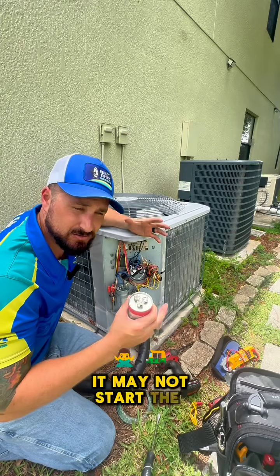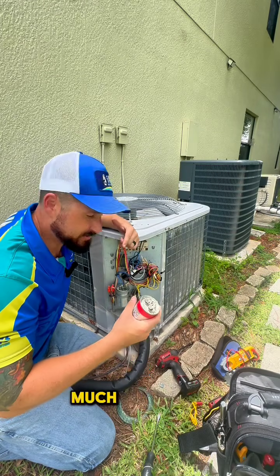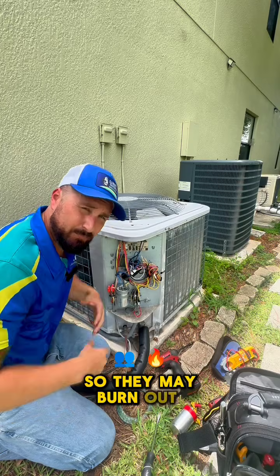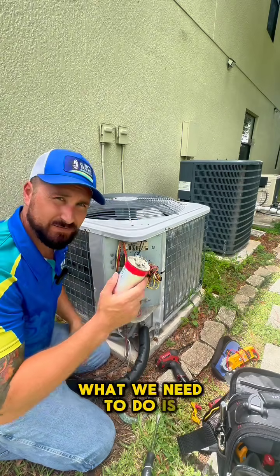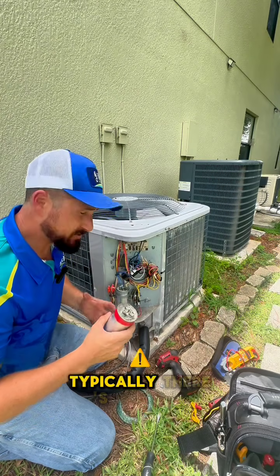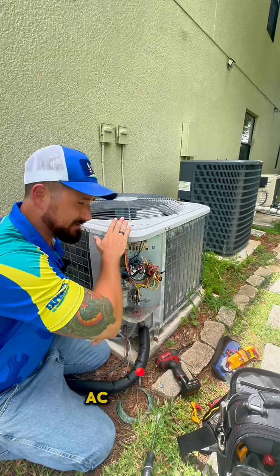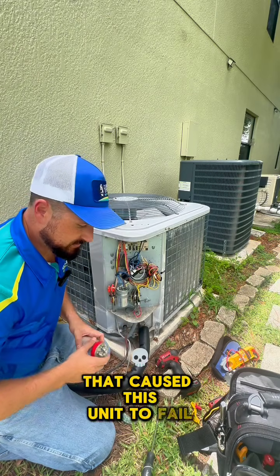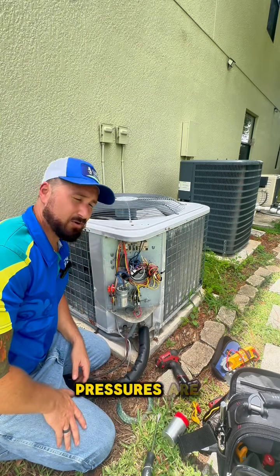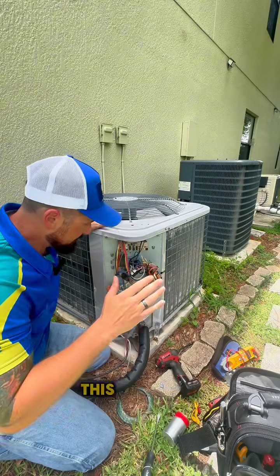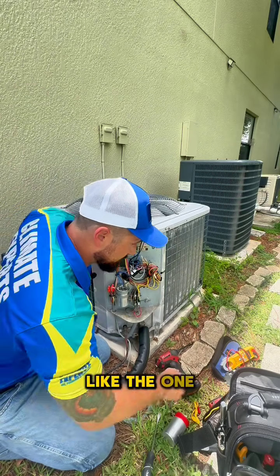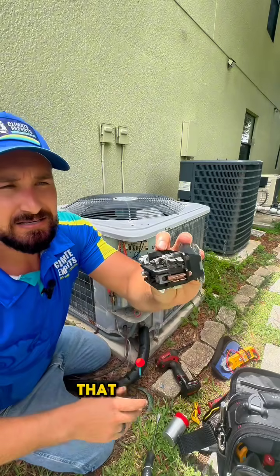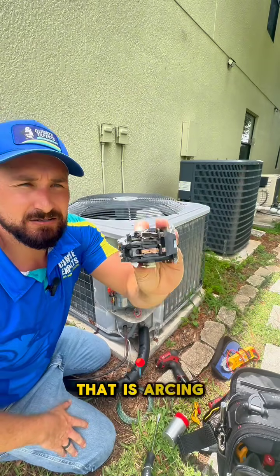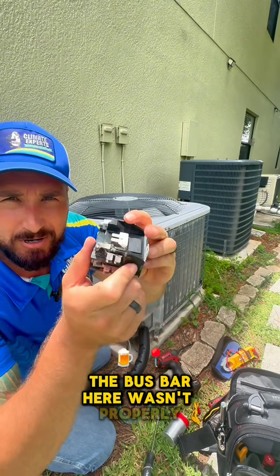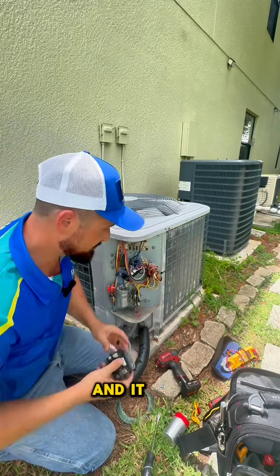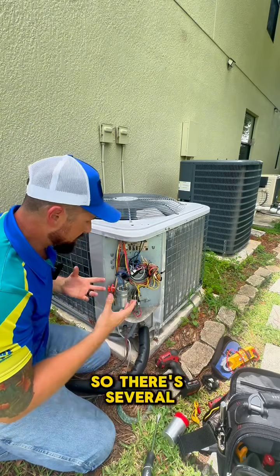It may not start the motors, or they may be pulling too much amperage, so they may burn out, pulling more power. What we need to do is find out why this failed. Typically, there's another issue within this AC unit here that caused this unit to fail. So this could be refrigerant pressures are low, causing this unit to overheat. This could be that we have a contactor, like the one we just replaced here, that is arcing here. The bus bar here wasn't properly attached to this lug and it was causing it to arc. So there's several things that could be causing it.